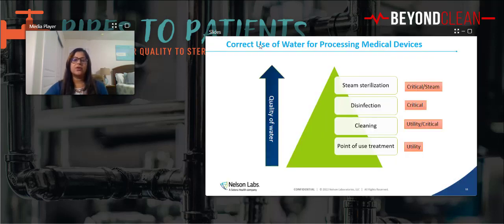Just to give you perspective of correct use of processing: steam sterilization critical, disinfection critical, cleaning utility critical. The last phase of cleaning should be done with critical, some sort of treated water—usually RO/DI water—and point of use is utility water. So the quality of water increases as the stages of reprocessing move forward. You want to remember this pyramid scale when doing reprocessing.